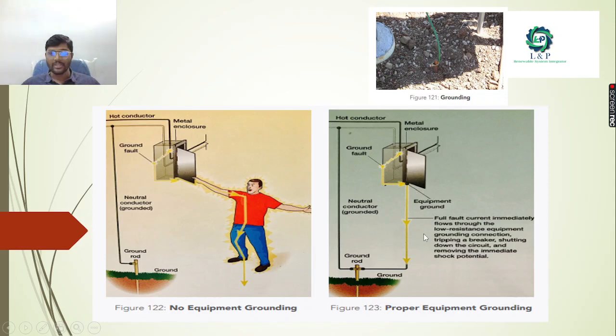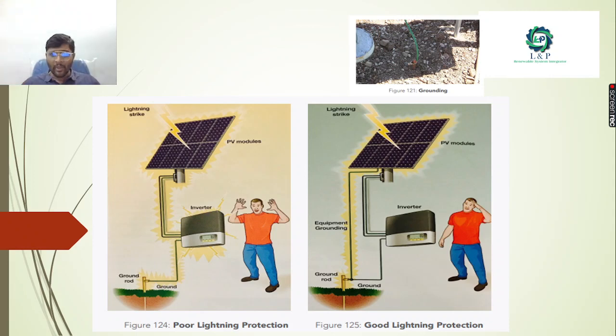So instead of that, always go for equipment groundings also. Okay, so on the AC side you need to do the groundings properly, and on the DC side you need to do the groundings properly. Even lightning protection you need to perform well. If lightning strikes the PV modules and they are grounded properly, it will go to the ground rod.